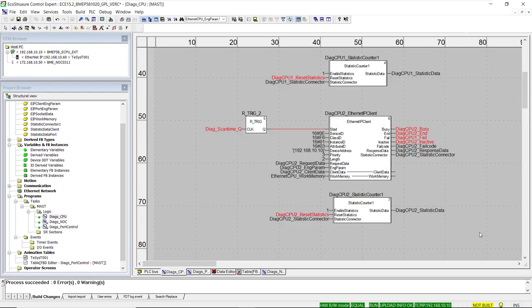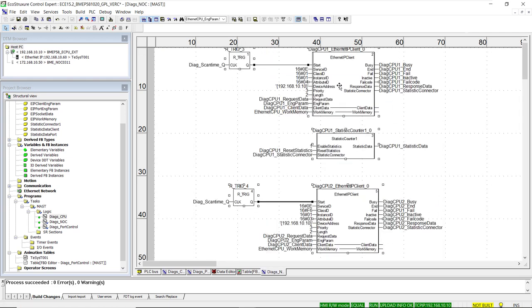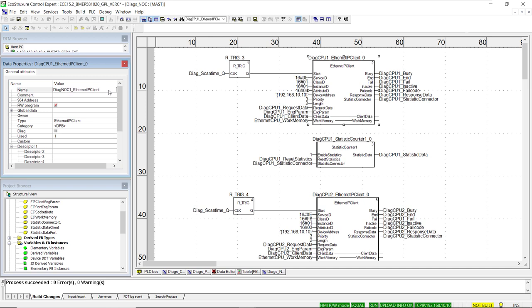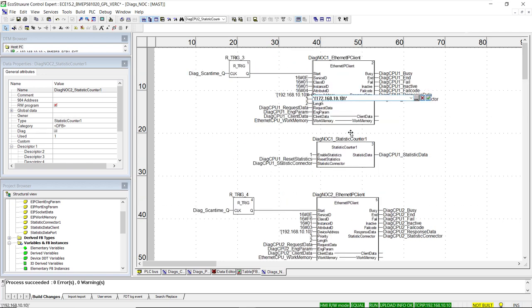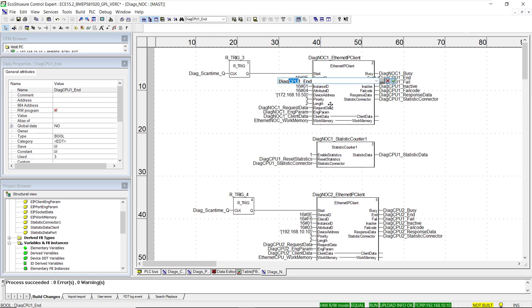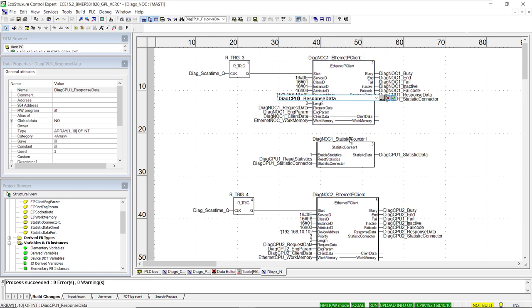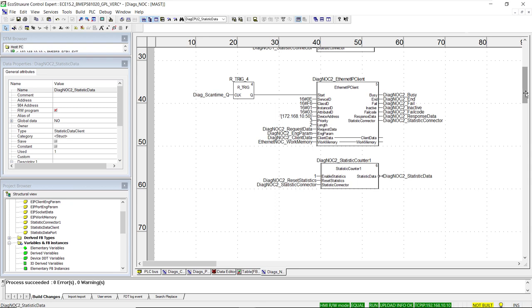We copy and paste logic from the CPU section into the new section for NOC module diagnostics, then correct instance names for each function block. The IP address is replaced with the NOC module's IP address, and all variable prefixes are updated to diag noc1. We continue updating variables on output pins of the first Ethernet IP client function block and the statistic counter. The first function block reads the firmware version of the NOC module, and the second obtains the MAC address.